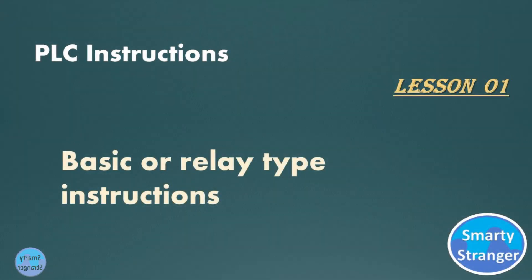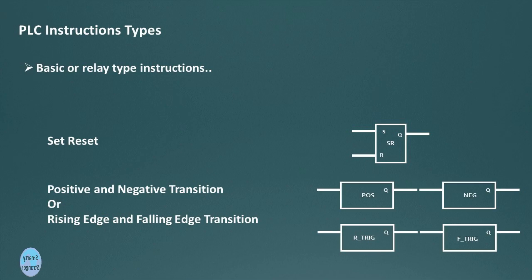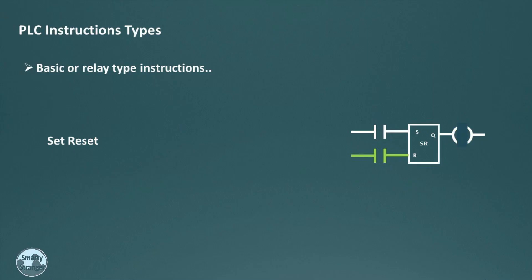Now we will talk about other basic or relay-based instructions: set and reset instructions, and positive and negative transition — also called rising edge and falling edge detection instructions. In the set-reset instruction, if the condition at the S input is momentarily on, the corresponding bit in the output data memory is set high and remains high until the R pin is set to high.